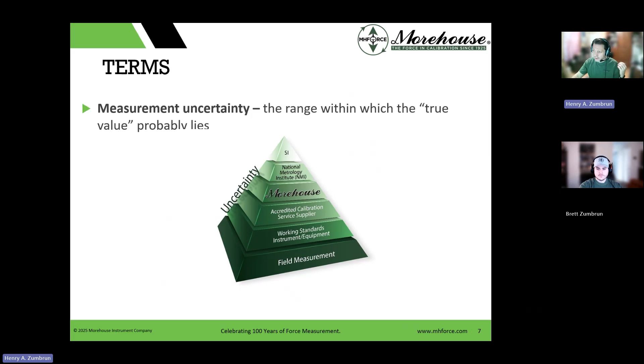I'm sick of saying it, but there's language in contracts that say it. So nothing is traceable to NIST directly. It's traceable to the SI units through an NMI, and they're documented. As this goes, you can see the uncertainty gets larger. Measurement uncertainty, typically the CMC uncertainty parameters, are defined in several documents. ILAC P14 is one of those.